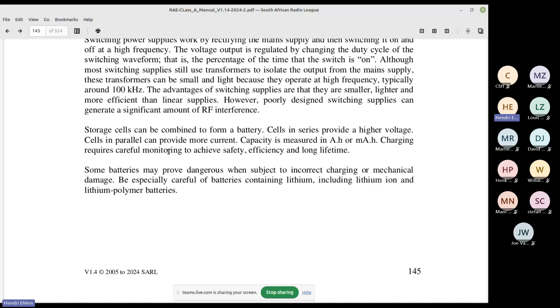But they usually have a C rating. Now, the C rating tells you how fast that battery can be discharged. C1 would usually mean that the battery can be charged as fast as it can be discharged. Now, if you look at a 100 amp hour deep cycle lithium battery, it's 100 amp hour, but a person must look very carefully, because you cannot necessarily draw 100 amps out of it. Some can handle more, some can handle less. So if you're going to connect a 2 kilowatt inverter to a 100 amp hour battery, check the battery, do the math, and then decide whether your battery will be able to handle the maximum current that your inverter will draw.